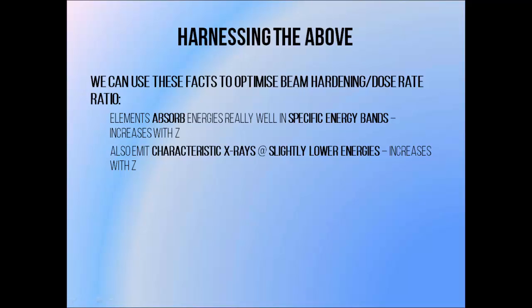We can harness the information on the previous two slides in order to optimize our beam filters to produce maximal beam hardening with minimal dose rate reduction. I mentioned that each atom is better at absorbing photons via the photoelectric effect within a specific energy range. I also mentioned that each atom produces characteristic X-rays within a specific energy range as well. This tends to be slightly lower than the energies at which absorption is increased. Both of these effects occur at higher energies as the atomic number increases.